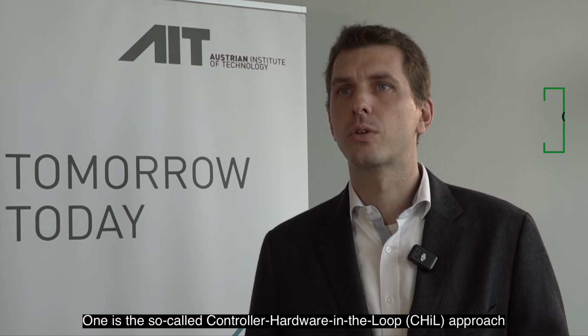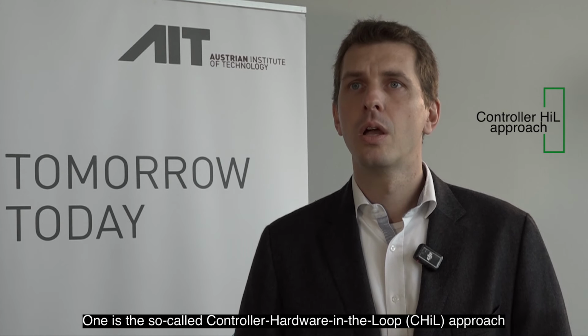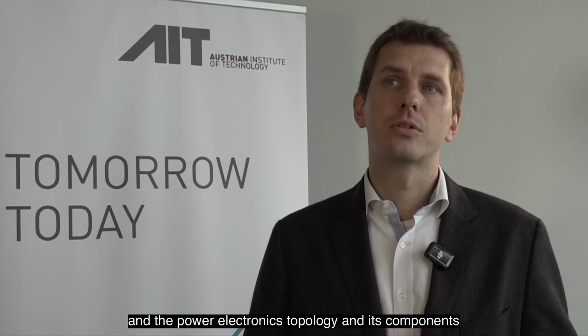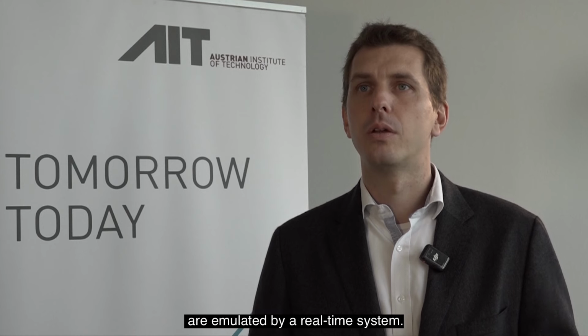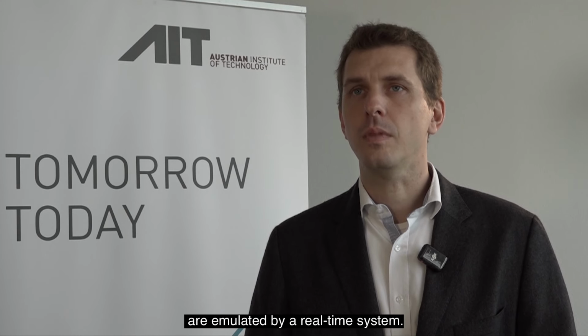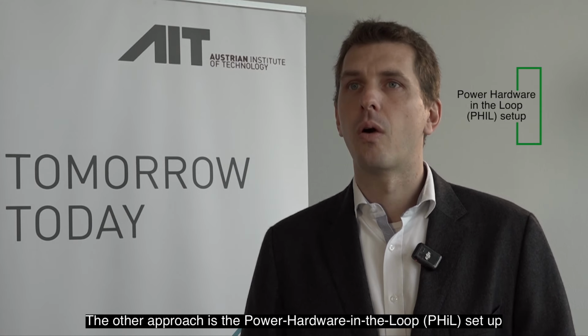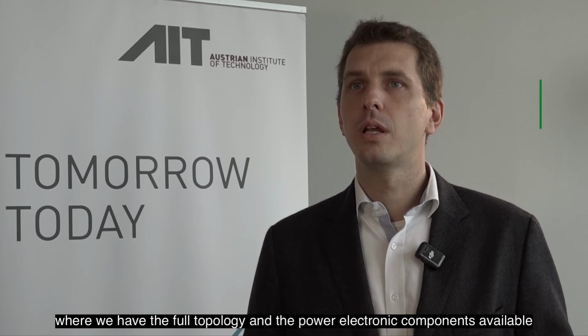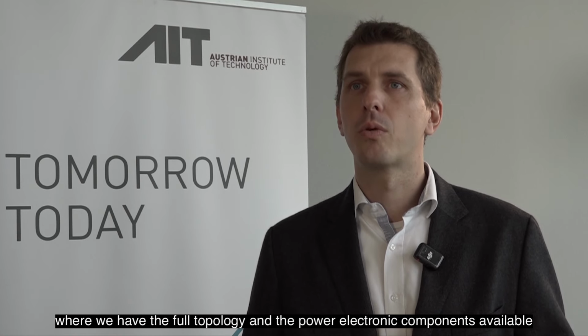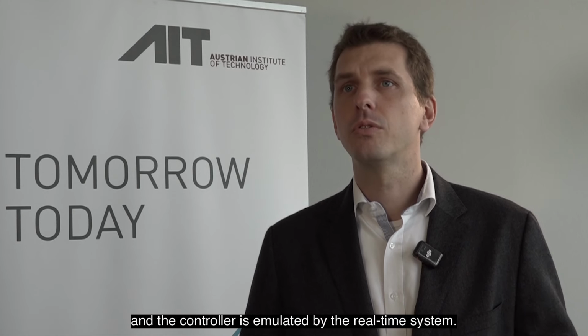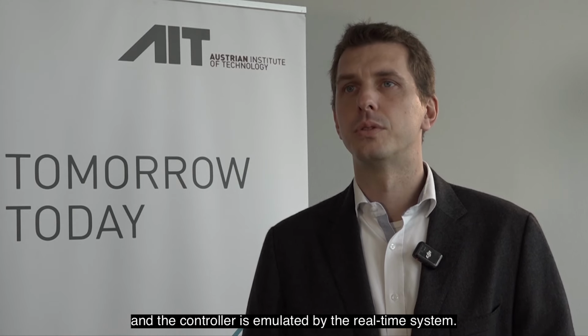One is the so-called controller hardware-in-the-loop approach, where we have only the controller physically available, and the power electronics topology and its components are emulated by the real-time system. The other approach is the power hardware-in-the-loop setup, where we have the full topology and the power electronics components available, and the controller is emulated by the real-time system.